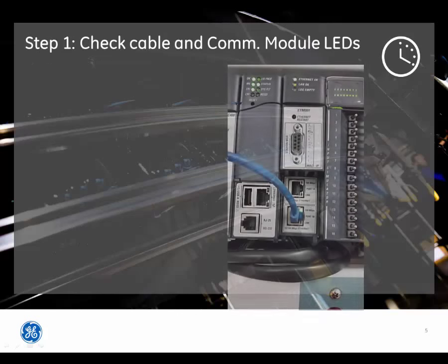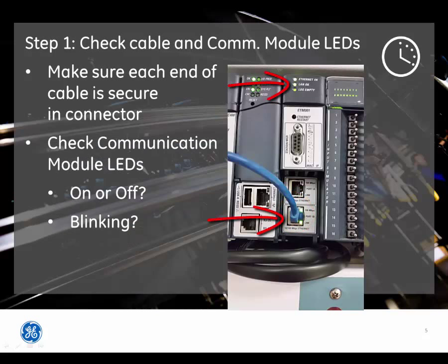For Step 1, check the communications cable and communication module LEDs. Make sure each end of the cable is secure in the connector. Check the communication module LEDs — are they on or off? Are they blinking? These all provide clues as to why communications is not working.